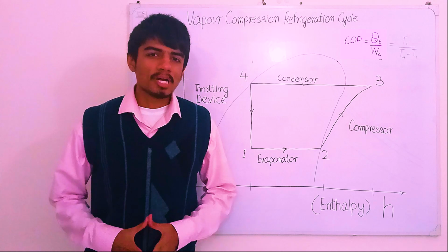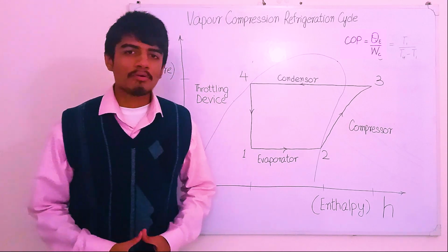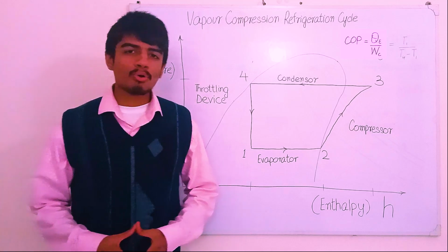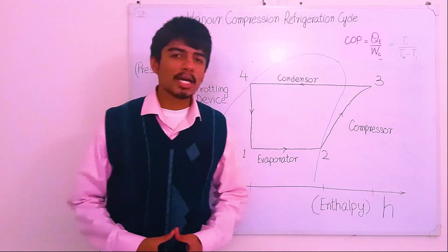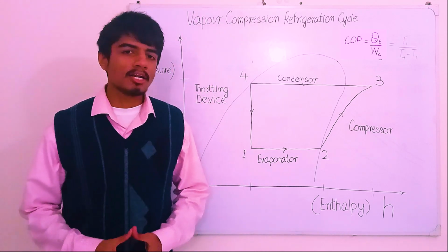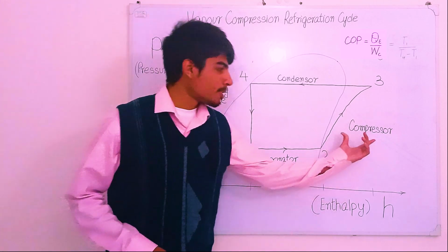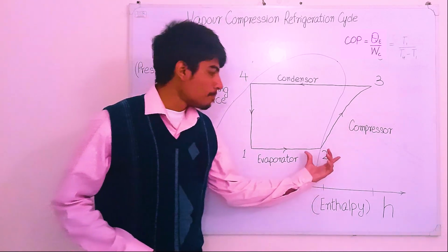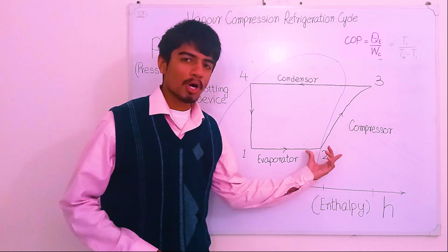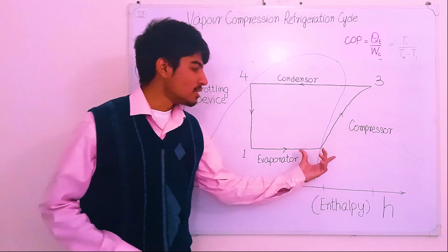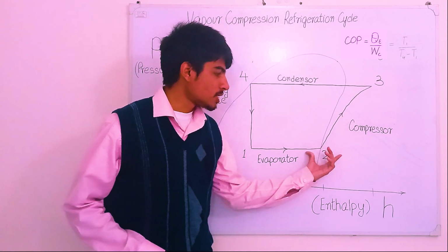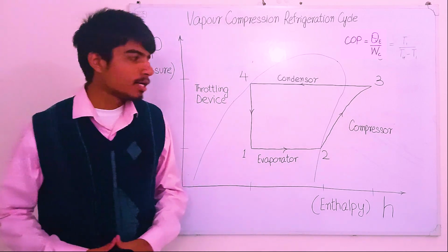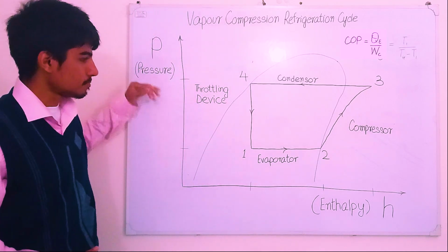Different types of compressors are used for compression of refrigerant. In case of air conditioners, scroll, rotary and reciprocating types of compressors are widely used. In compressor, mechanical energy is required to compress low pressure, low temperature refrigerant which is in saturated vapor state in order to reduce its volume and increase its pressure.